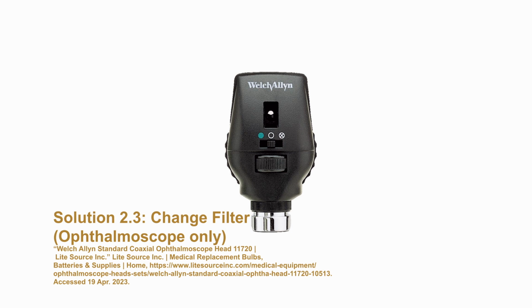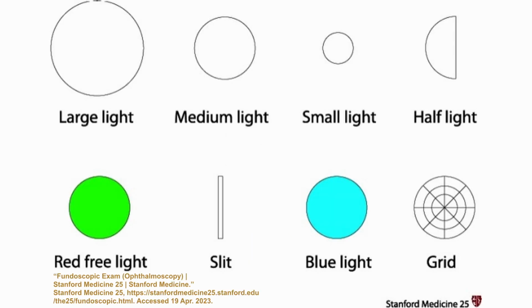Ophthalmoscopes have different filters for different uses. This is controlled by the filter switch on the front of the head above the aperture dial. The red free filter is used to look closely at vasculature. The blue filter is used to look for corneal abrasions or ulcers with fluorescein dye.